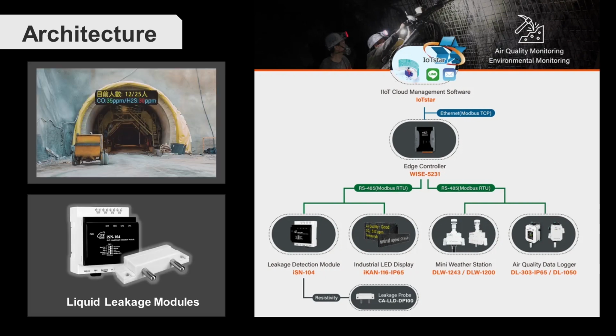The ISN104 liquid leakage detection module and liquid leakage probe are also installed to monitor water leakage in tunnels. The collected data are then transmitted to the WISE5231 edge controller through Modbus RTU, and then are sent to IoT Star in the control center to achieve remote visualization monitoring. In addition, the client installs an iKAN industrial LED display to show multiple environmental data, allowing on-site personnel to keep abreast of the work environment conditions in real time.